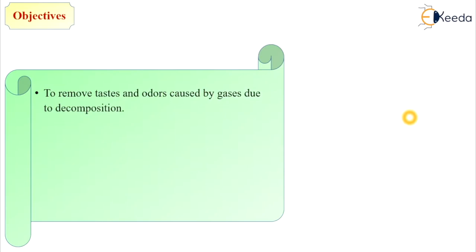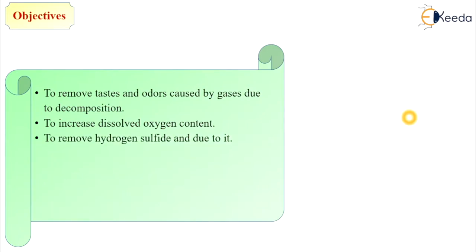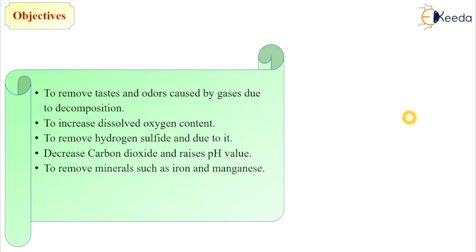The objectives of providing aeration are: to remove taste and odor caused by gases due to decomposition; to increase dissolved oxygen content, as there is a minimum requirement of dissolved oxygen in drinking water; to remove hydrogen sulfide gas, decrease carbon dioxide, and raise the pH value; to remove minerals such as iron and manganese — because of aeration, these metals in ion form get oxidized into a stable form; and due to agitation of aeration, pathogenic bacteria may get killed.